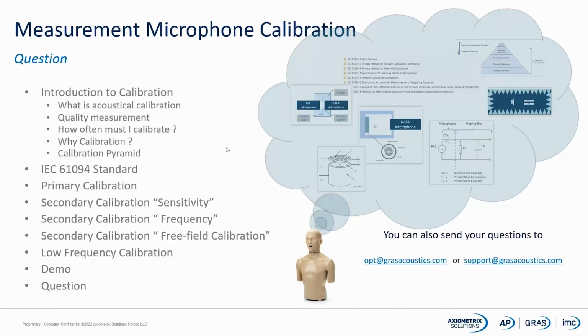Any warm-up time needed before starting and using an electrostatic actuator or analyzer? Yes, there is a warm-up time. We recommend half an hour when you switch on your system, and half an hour before you would like to use it. The microphone itself also has a warm-up time, especially an externally polarized microphone where you have the 200 volt polarization voltage. There's a time constant in the microphone, which takes some time before the microphone actually builds up the pressure. So that's something you have to have in mind.